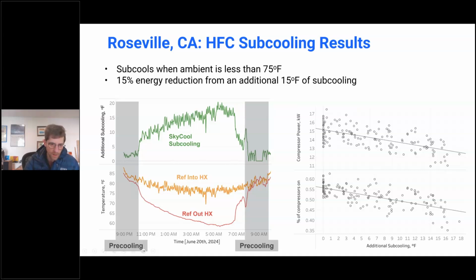And you can see here on the left just the amount of subcooling that we're providing. So it's going to vary as a function of time based on the ambient and the conditions of the site and the load in the equipment. But we're getting between 10 and 20 Fahrenheit of subcooling in a given period when it's running.